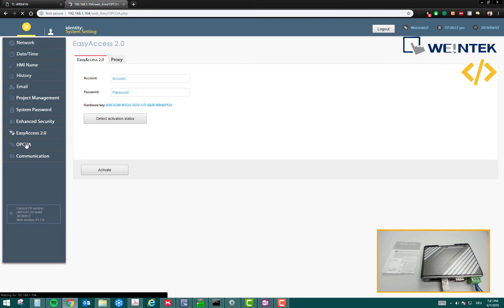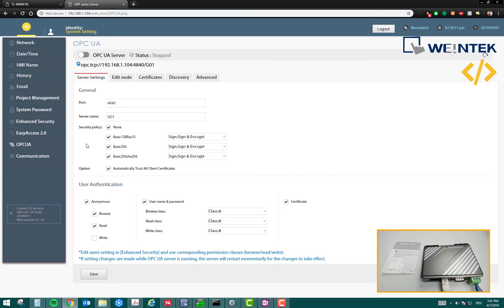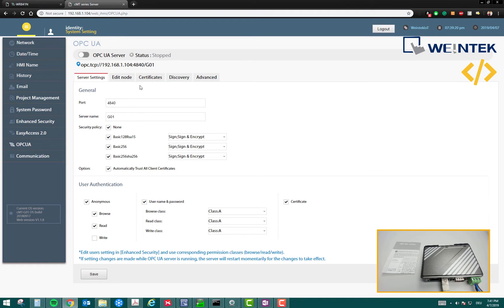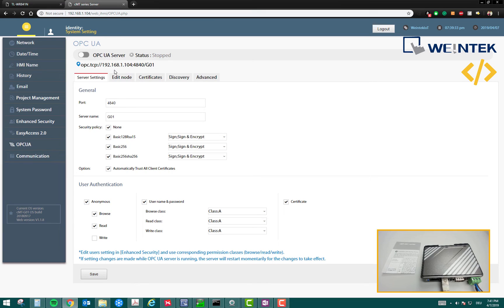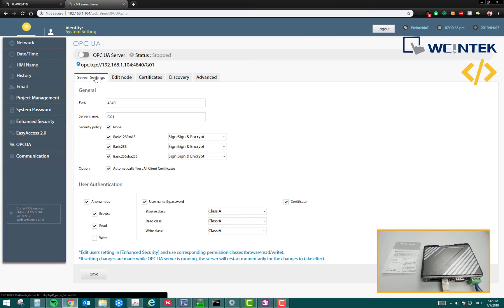Then we come to OPC UA. OPC UA is a protocol by which you can connect this device to various controllers. That controllers could be a PLC or any controller which supports the communication ports, which is RS-232, RS-485 or Ethernet. Suppose I have a PLC, which I will connect to my device in the future videos. That PLC will send the tags to this device. Then this OPC UA server will assign a unique name to these tags, which you can access using OPC client. This is a very good example which we are going to see in the future videos.